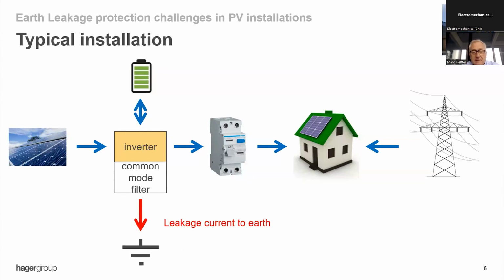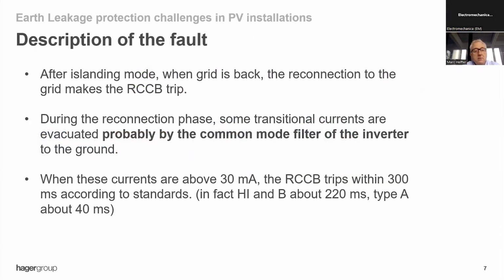When an RCCB trips, it's because of an earth leakage. Each inverter has a common mode filter. What we think is that when the grid comes back, there are some transition currents that are filtered by this common mode filter and generate some leakage. This leakage is seen by the RCCB, and therefore it trips. That is what is written here. We suppose it's probably due to this common mode filter, but we'll see this later on. We have to investigate a little deeper to be sure that's the right analysis of the situation.